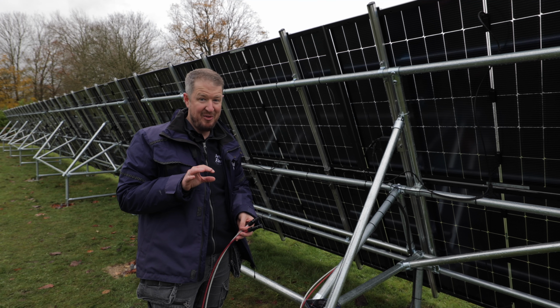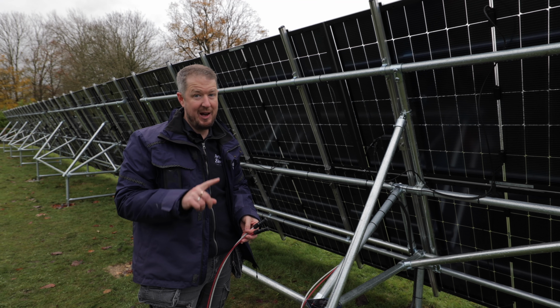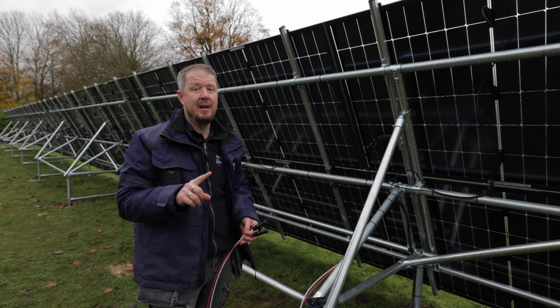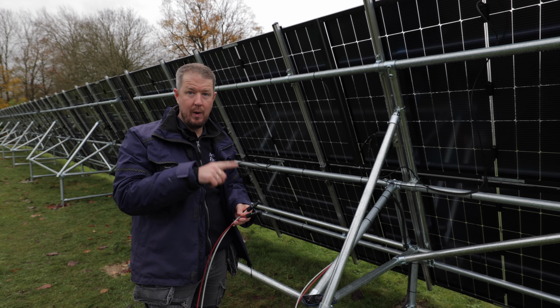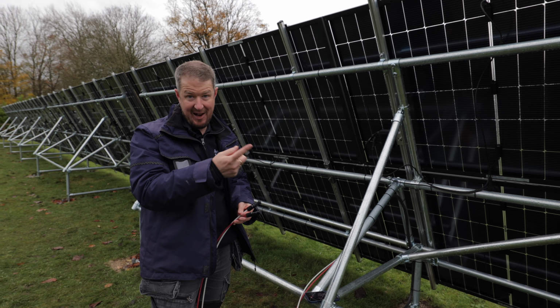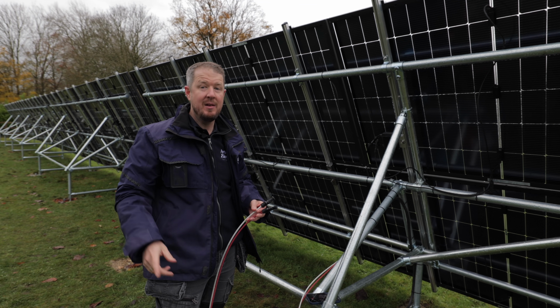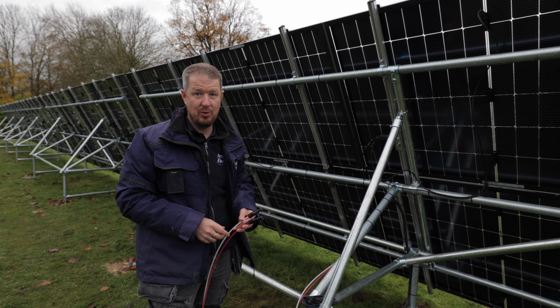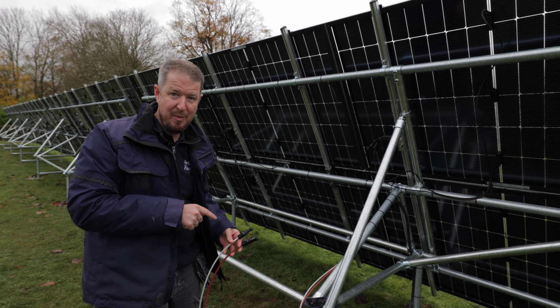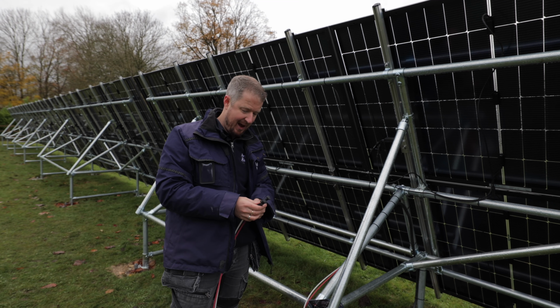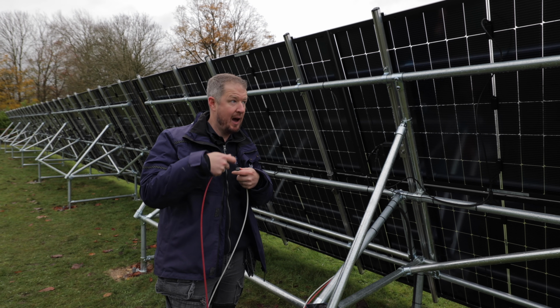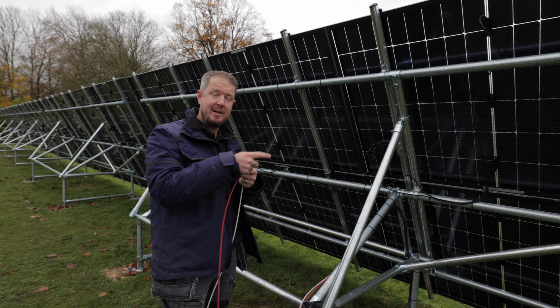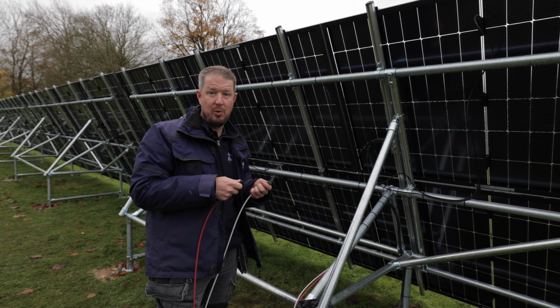This is now the moment of truth where we test the cables to make sure there's no damage, and to figure out which cable is which at each end so we can connect them in the correct order in the inverter. I'm going to get Ruben on loudspeaker - he'll test at that end, then I'll plug these in, and we'll know from a continuity test at that end which cable is which.